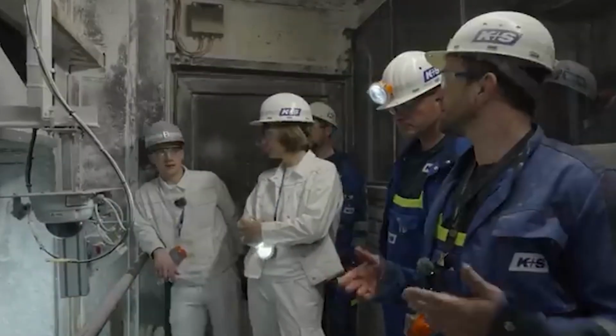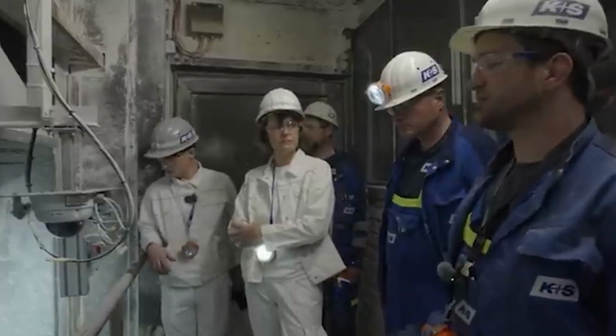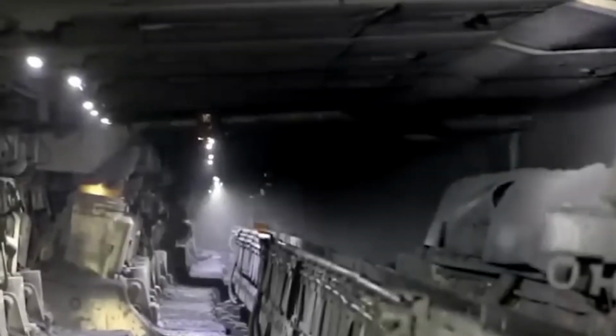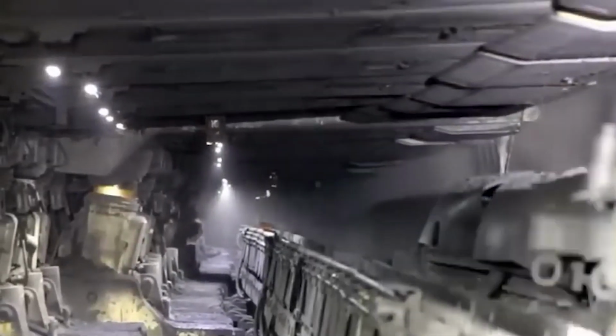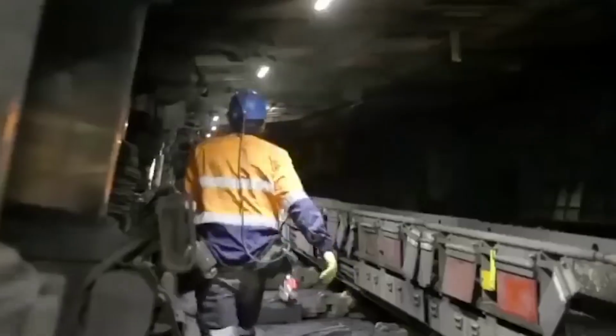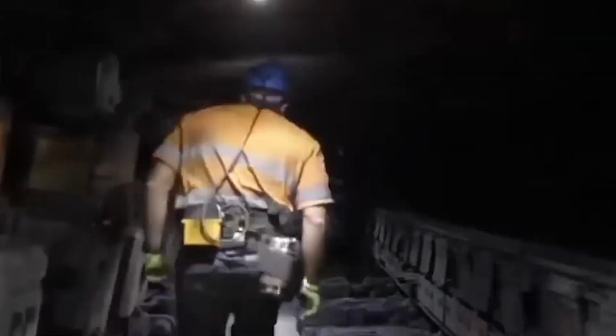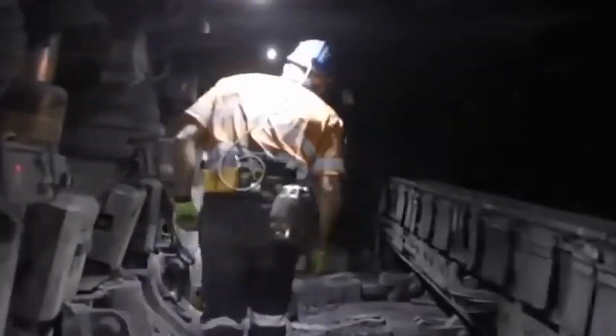Mechanical refrigeration becomes the primary life support system. The chilled water infrastructure transforms from a supportive system to a critical one. Industrial cooling plants on the surface operate continuously, consuming enormous amounts of electrical power to chill water that will be pumped 2,000 meters straight down. These aren't residential air conditioning units scaled up; they're systems designed for major commercial buildings, but operated around the clock to support underground operations.